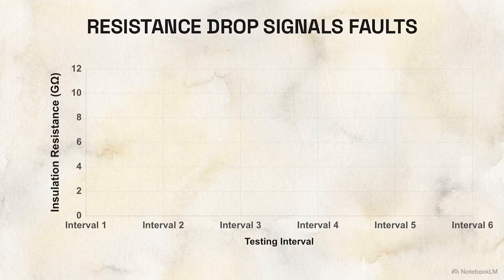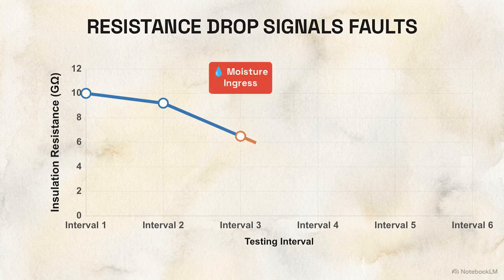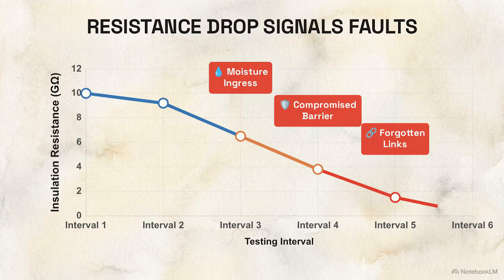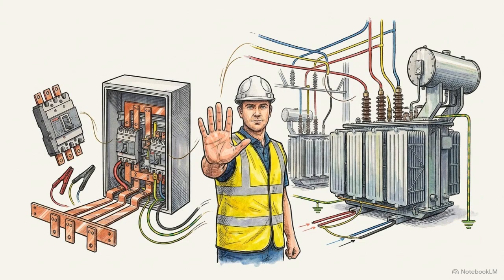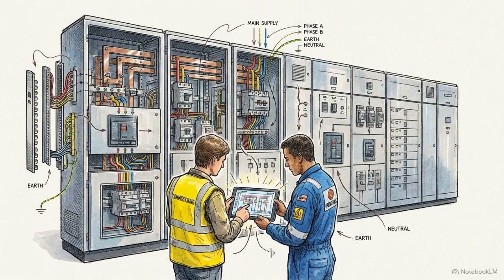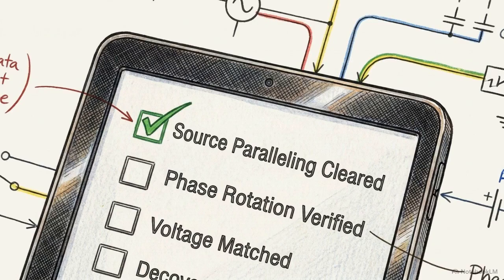Engineers analyze insulation resistance data for downward trends. A drop in resistance indicates a root cause like moisture ingress, compromised insulation barriers, or forgotten temporary test links. An engineer proves their value by recognizing these critical deviations and exercising their authority to halt the process immediately. Before the system can be released, operations and commissioning witnesses must clear a final hold point. They confirm absolutely no unintended source paralleling occurred during testing and verify that no protection schemes remain blocked.